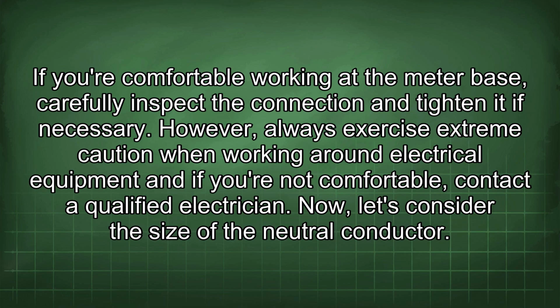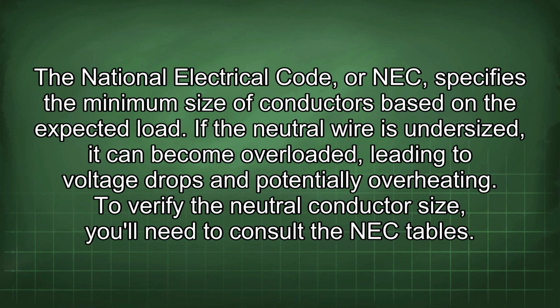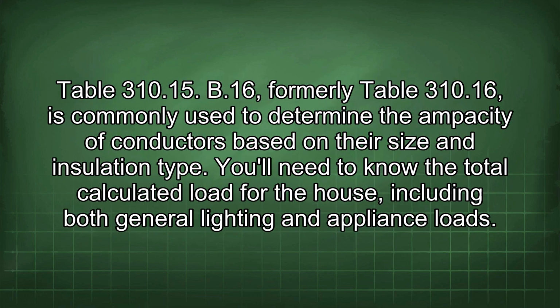Now let's consider the size of the neutral conductor. The National Electrical Code, or NEC, specifies the minimum size of conductors based on the expected load. If the neutral wire is undersized, it can become overloaded, leading to voltage drops and potentially overheating. To verify the neutral conductor size, you'll need to consult the NEC tables. Table 310.15(B)(16), formerly Table 310.16, is commonly used to determine the ampacity of conductors based on their size and insulation type. You'll need to know the total calculated load for the house, including both general lighting and appliance loads.